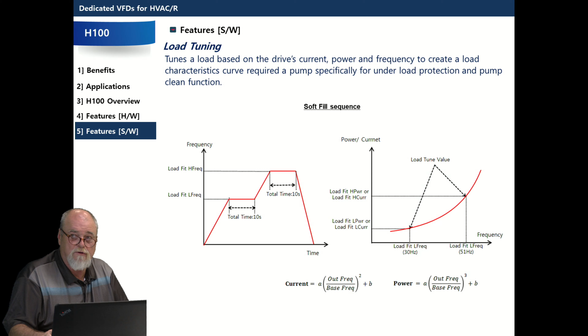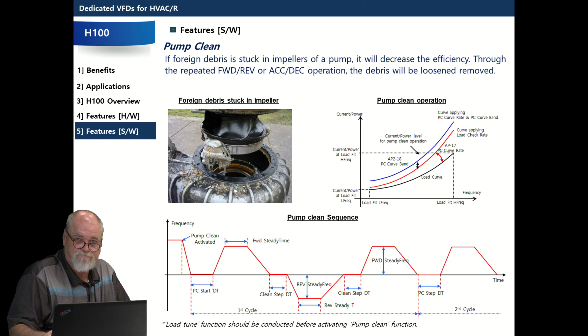That's one of the reasons why we do load tuning. With the pump clean, we can determine that the inlet of the pipe is clogged. So, as you can see from the graph, we will slow down, run in reverse, run back up. If it's still there, we continue. You can set limits to where we're trying to clear the obstruction, so thereby you can start to run. And that's based on the load tuning. Under load conditions, we have that as well.